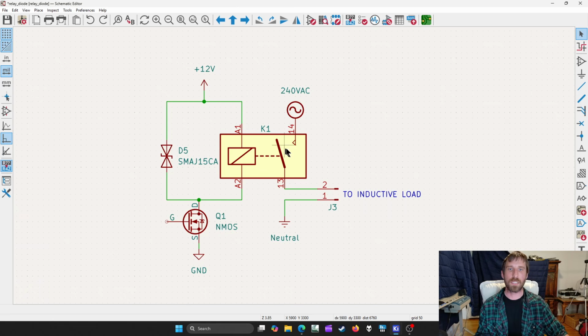So what's going on here is an unprotected relay. If you're going to do this, you need to overspec your relay, but we found that even overspecking quite a bit can cause failures, enough failures that it's unacceptable. But in plenty of circumstances, it will last practically forever.